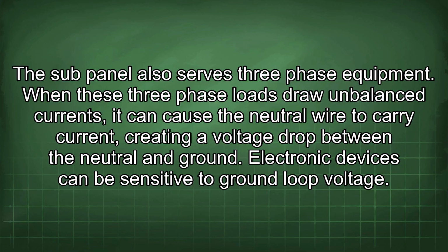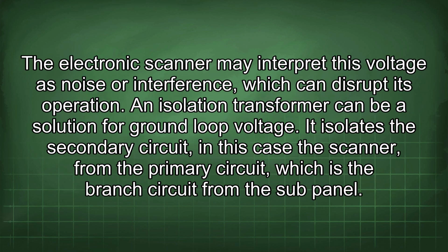Electronic devices can be sensitive to ground loop voltage. The electronic scanner may interpret this voltage as noise or interference, which can disrupt its operation. An isolation transformer can be a solution for ground loop voltage.